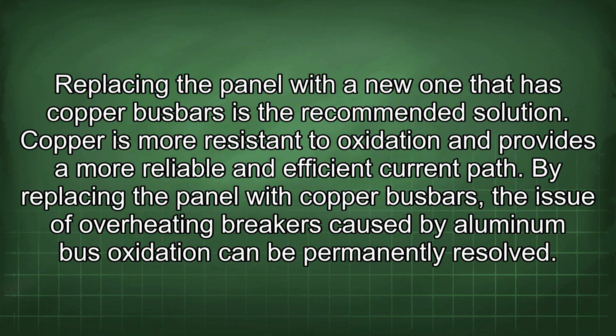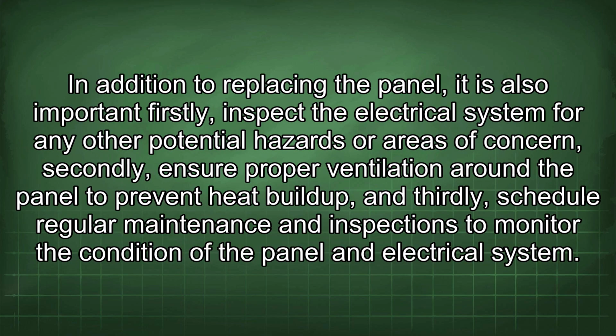Replacing the panel with a new one that has copper busbars is the recommended solution. Copper is more resistant to oxidation and provides a more reliable and efficient current path. By replacing the panel with copper busbars, the issue of overheating breakers caused by aluminum bus oxidation can be permanently resolved. In addition to replacing the panel, it is also important, firstly, to inspect the electrical system for any other potential hazards or areas of concern. Secondly, ensure proper ventilation around the panel to prevent heat buildup. And thirdly, schedule regular maintenance and inspections to monitor the condition of the panel and electrical system.